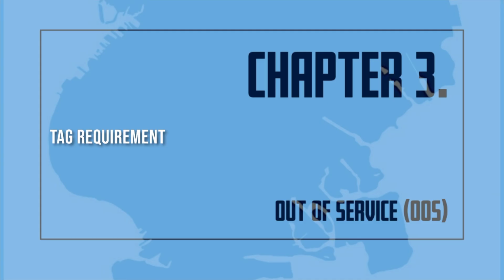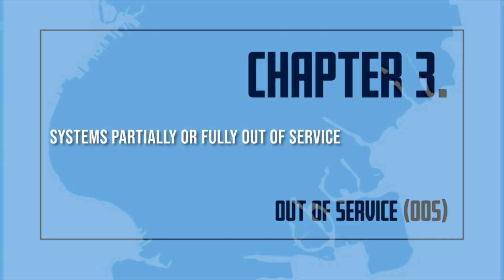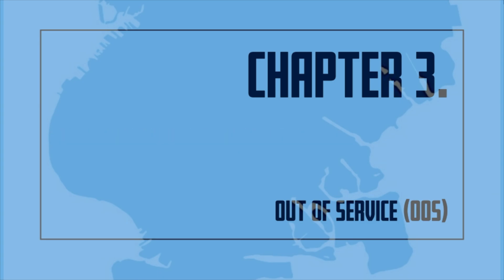Drain test results shall be posted on the tag indicating both the static and flow pressures before and after the system was placed in an out-of-service condition. If no impairment is found in the entire system, green tags will be placed on the main control valve. Systems partially or fully out of service. Fire suppression piping systems equipped with fire department connections shall follow the following procedures for identifying systems out of service.